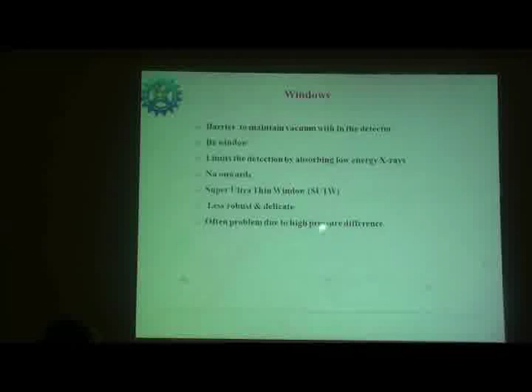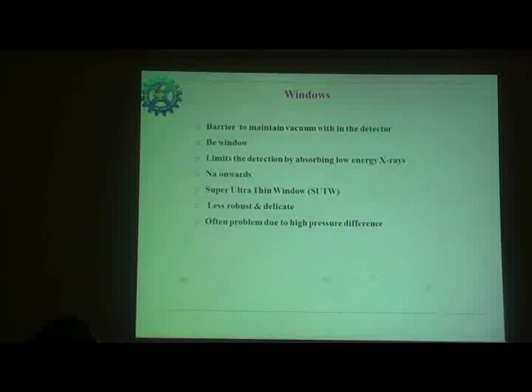So you have the window before reaching the detector. That is the barrier to maintain vacuum with the detector. You have a beryllium window, which is transparent to most X-rays. But this can limit the detection by absorbing low energy X-rays. So when you use a beryllium window, you can detect from sodium onwards. Nowadays you have still thinner windows, called super ultra thin windows, SUTW. It is made of organic polymer, but this is less robust and very delicate.